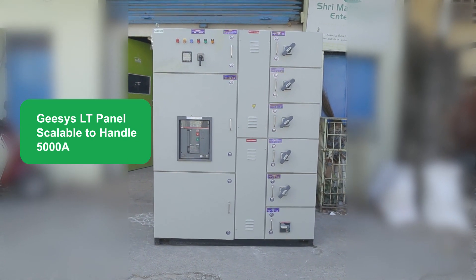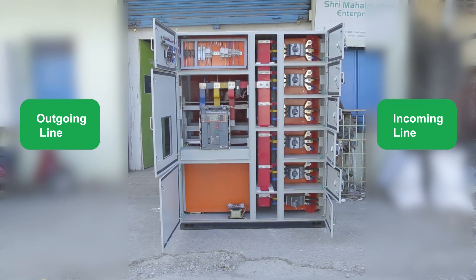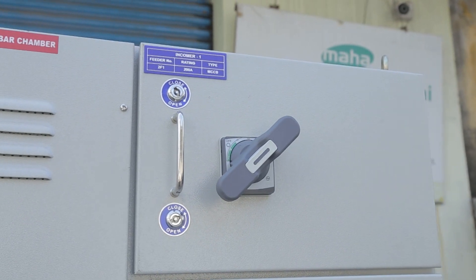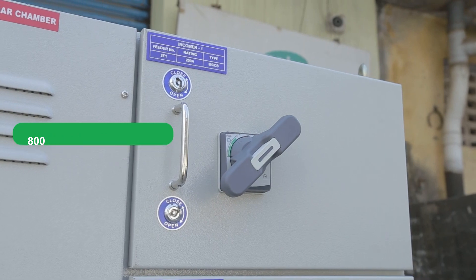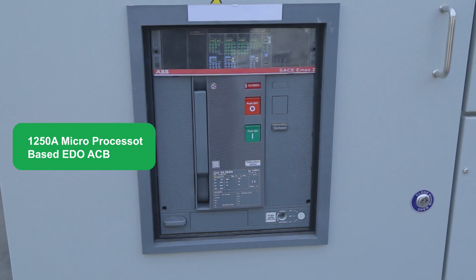Geesys LT panels are scalable to handle power requirements up to 5000A safely. Geesys AC combiner panels merge the output of multiple solar inverters into a single unified output, simplifying the connection to main distribution panels or to a transformer. Geesys recently manufactured and supplied a solar main LT panel for a 1MW solar power plant with 800-volt AC output. The panel has 5 inputs as incomers and 1 output as outgoing. The solar LT panel is connected to 4 numbers of 325kW solar inverters through 800-volt 320A TMT MCCB, and the outgoing is connected to the bus duct through a 1250A microprocessor-based EDO ACB.